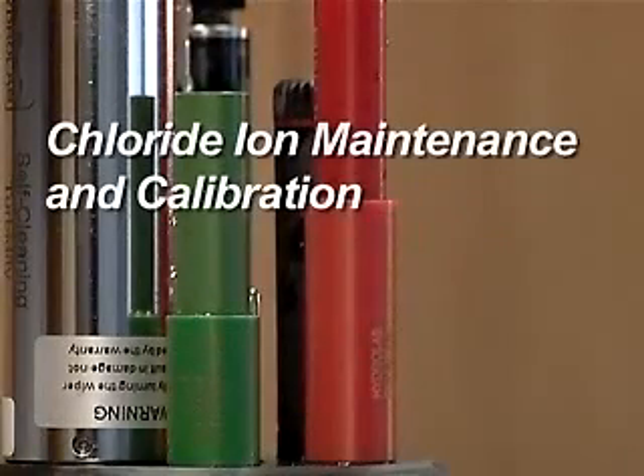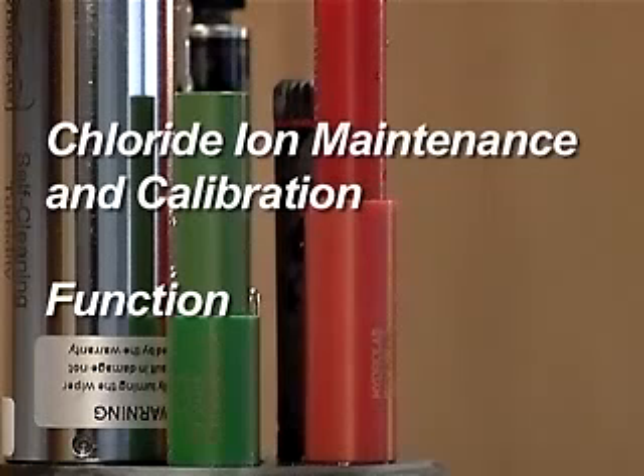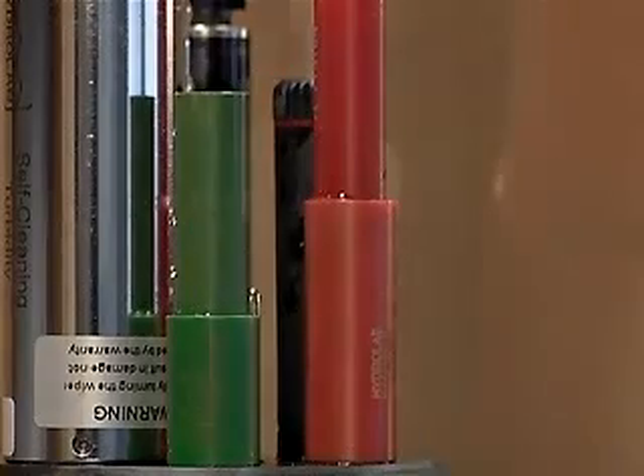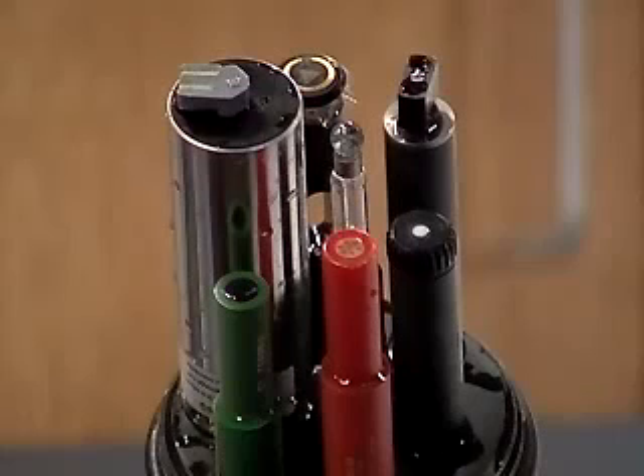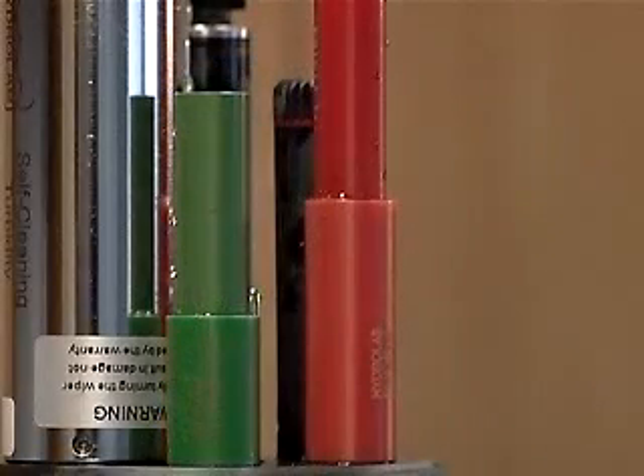Chloride ion maintenance and calibration. Function. The chloride ion sensor uses two electrodes to measure the electrical potential between a known ion concentration and the sample. The electrode on the sensor is a pellet of silver chloride in contact with the sample water. As the chloride ions dissolve from the pellet into the water, the excess silver ions build up an electrical potential that is measured with the reference electrode used by the pH sensor.